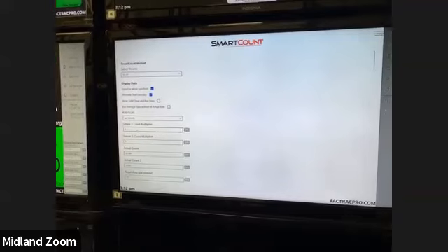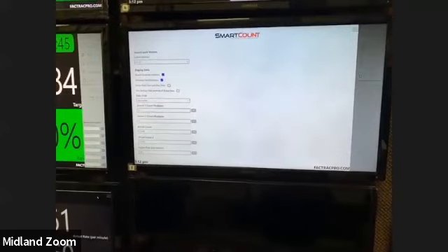Okay. Rate scale, you have the selection to choose per hour, per minute, or per second based on how they want to see the data. The count multipliers you have for both sensor 1 and sensor 2. In an example that Eric used where you have a case of 10 products going down the line and you're only counting the case. If there's 10 pieces in there and you want to actually count the total pieces, you can set that multiplier to 10. So every time that case is counted, it's going to increase the number by 10.